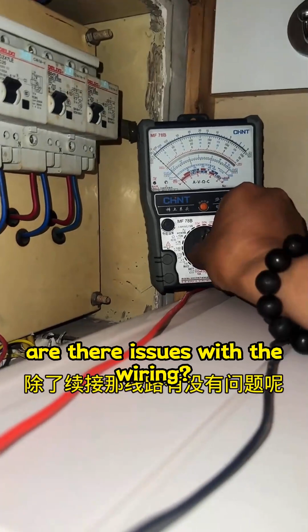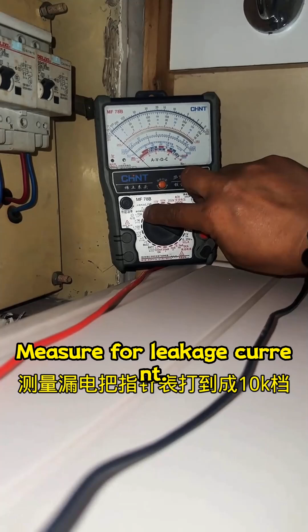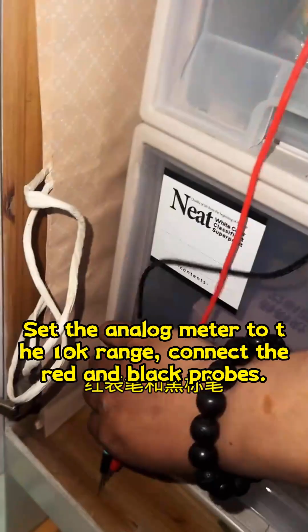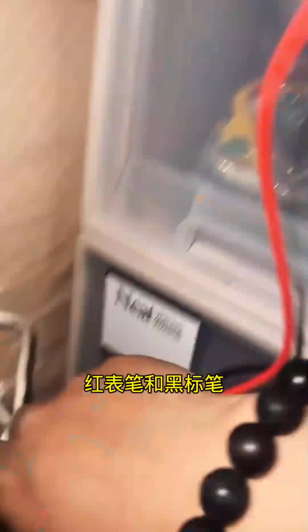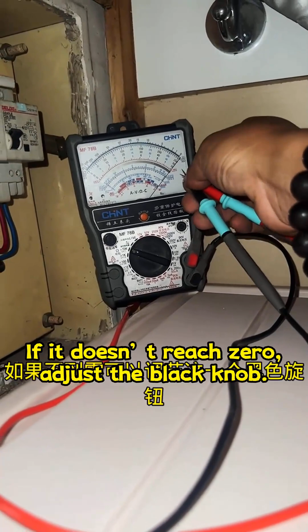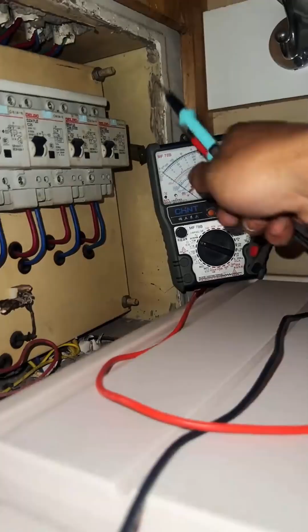Besides the loose connections, are there issues with the wiring? Leakage current can be measured. Measure for leakage current. Set the analog meter to the 10K range. Connect the red and black probes. Short the two probes together. Observe the needle's movement. Check if the needle goes to 0. If it doesn't reach 0, adjust the black knob. Set the needle to the 0 position.